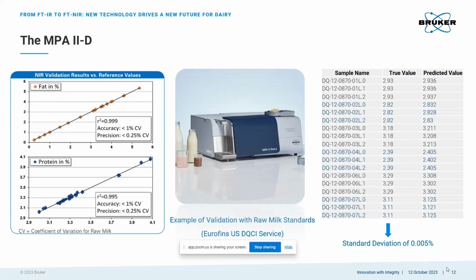Another thing to point out is that with this multi-purpose analyzer, we observe both phenomenal accuracy as well as repeatability. And we can see this when we look at the validation of our raw milk calibrations. The LSM module and the calibrations for raw milk were checked with certified standard milk sample sets from Eurofins' DQCI here in the US, that's what we're looking at. And what we're seeing is that these results show excellent accuracy and linearity for both fat and protein.